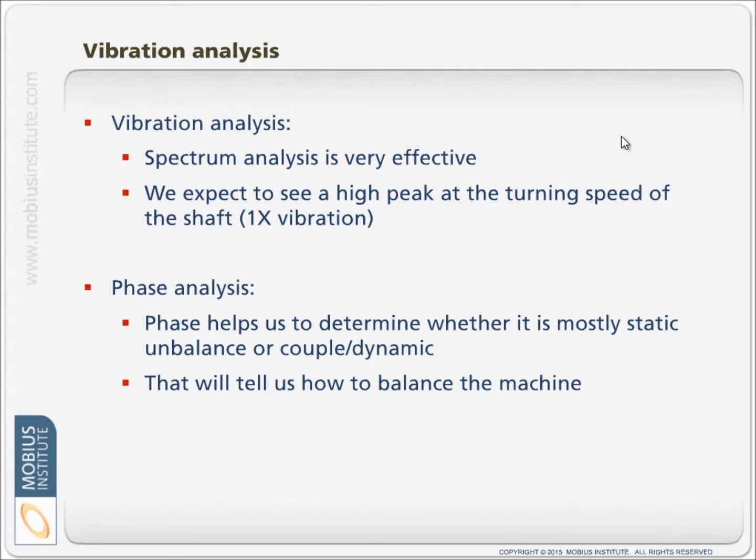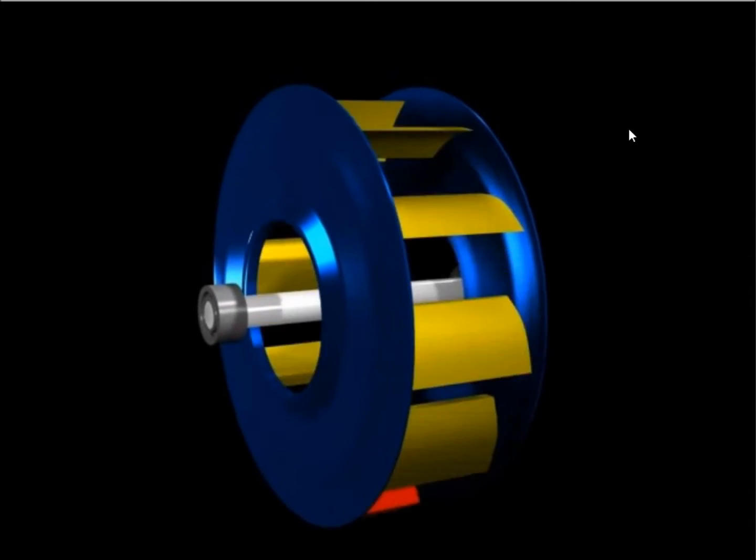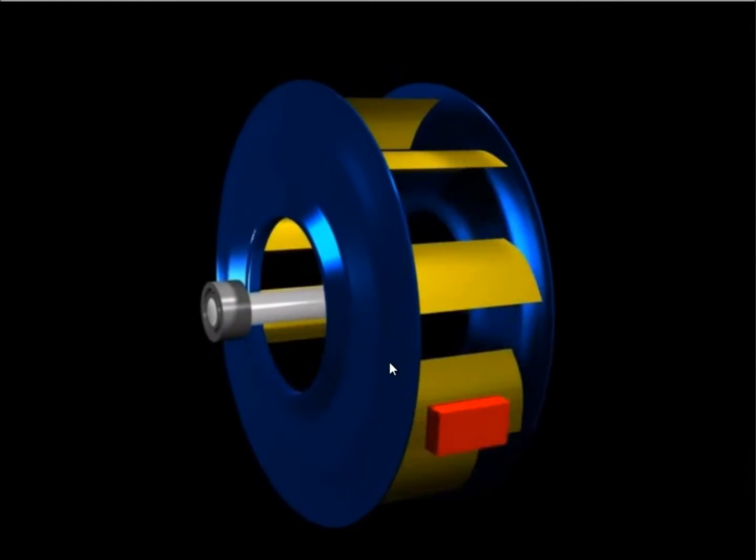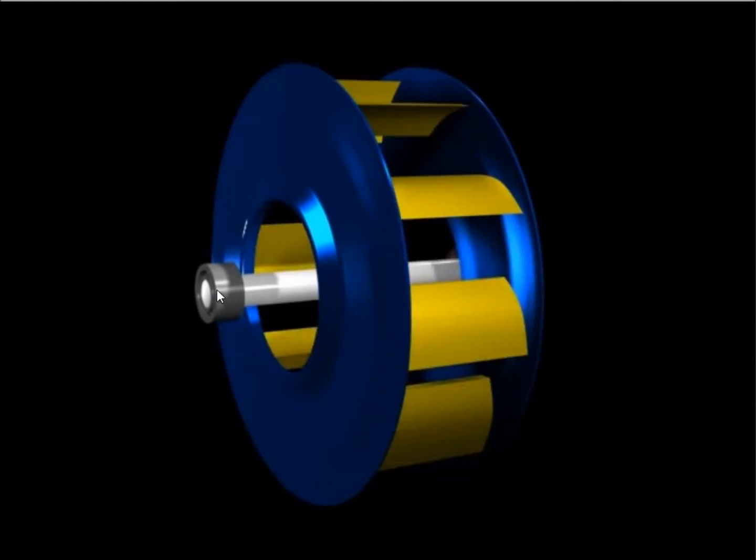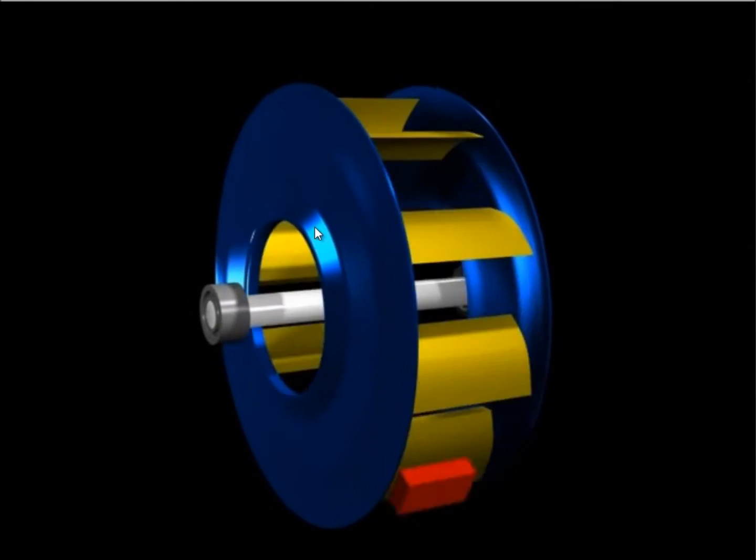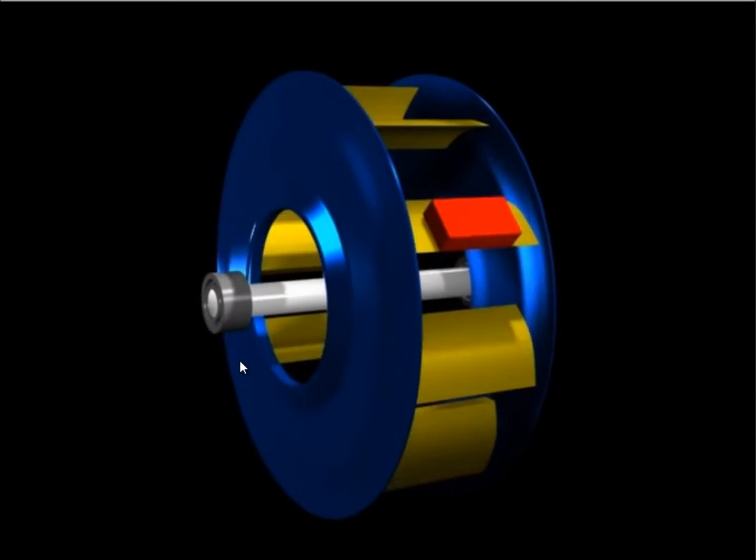If we have static unbalance, it's all in one plane. Number one, we see that the motion is at the running speed, so we see the high 1x peak.